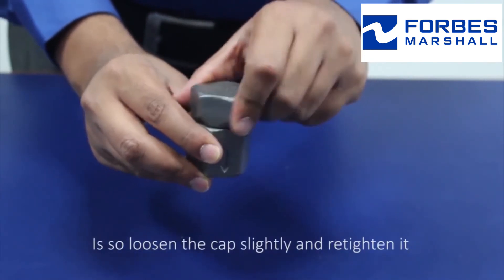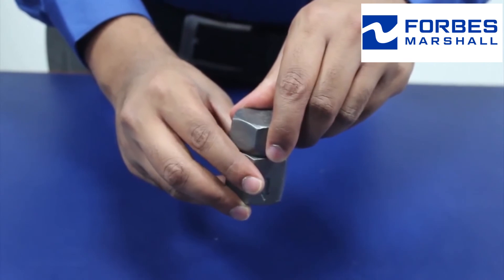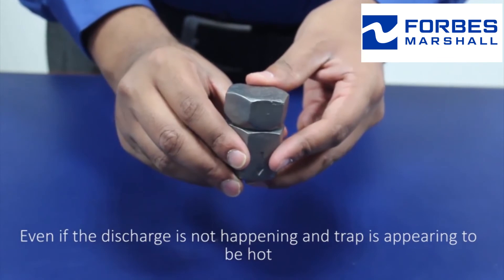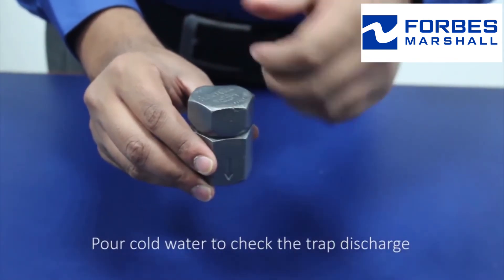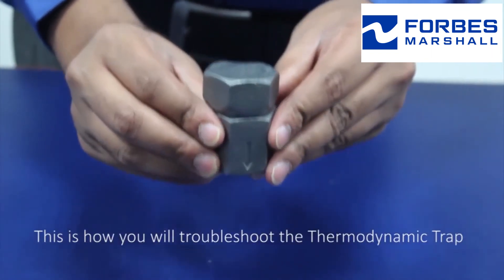If so, loosen the cap slightly and retighten it. Check for the discharge pattern. Even if the discharge is not happening and the trap appears to be hot, pour cold water to check the trap discharge. This is how you troubleshoot the thermodynamic trap.